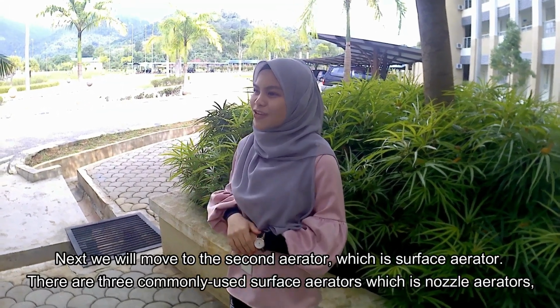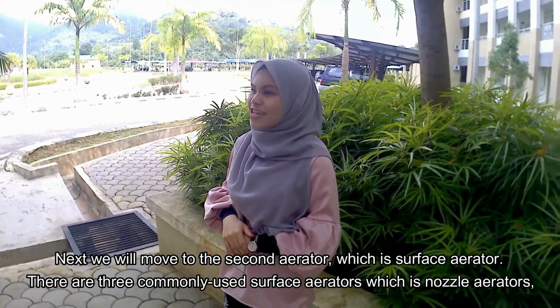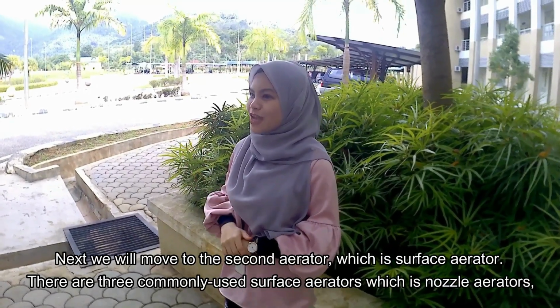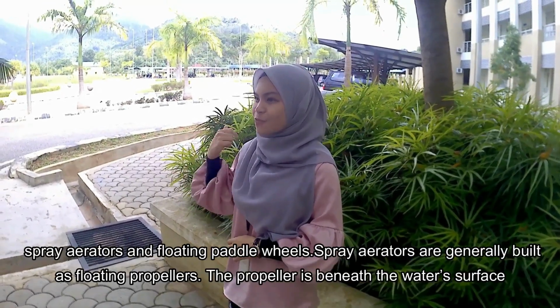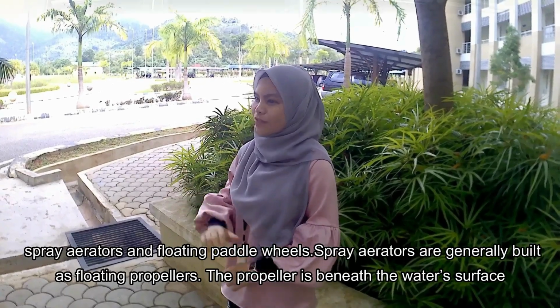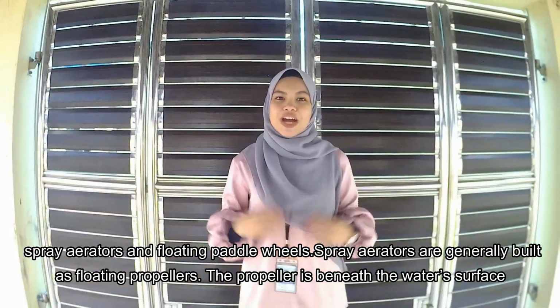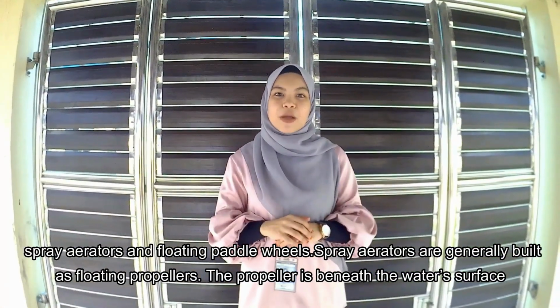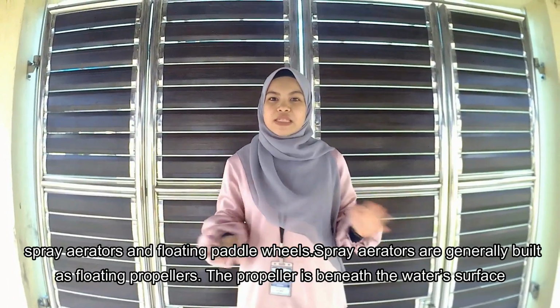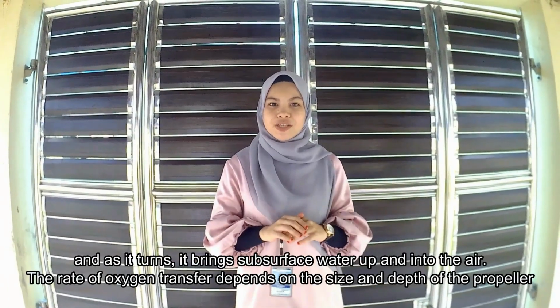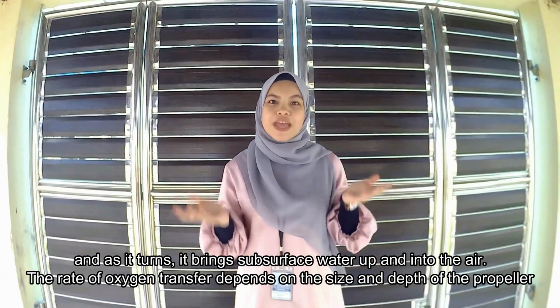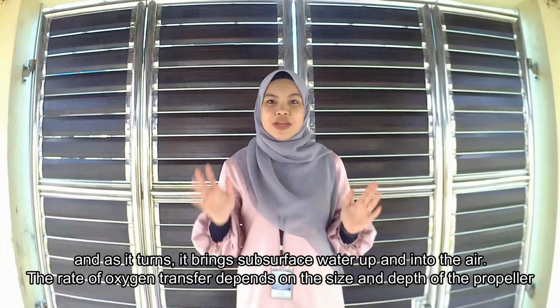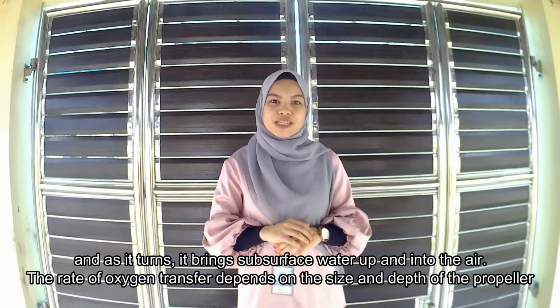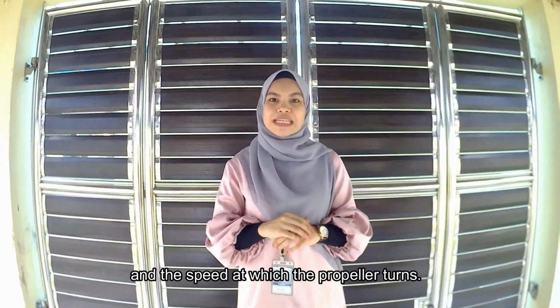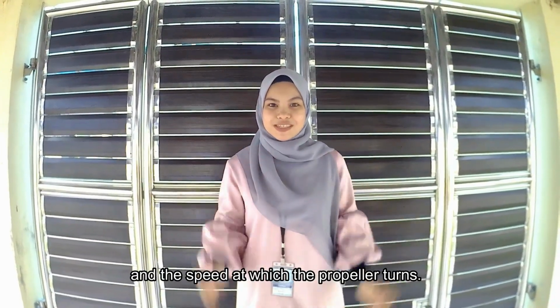Next, we will move to the second aerator, which is surface aerator. There are 3 commonly used surface aerators, which are nozzle aerators, spray aerators, and floating paddle wheels. Spray aerators are generally built as floating propellers. The propeller is beneath the water surface, and as it turns, it brings subsurface water up and into the air. The rate of oxygen transfer depends on the size and depth of the propeller and the speed at which the propeller turns.